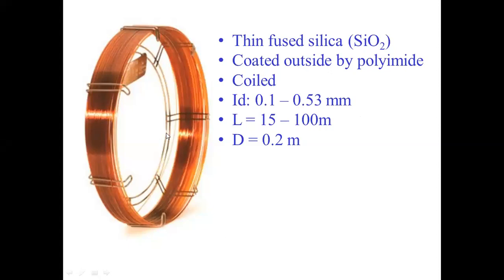And the intensity of this brownish color will fade away with time. So depending upon the intensity of this brownish color, we can decide whether the column is active or not, whether it is usable or not. The lifetime is also decided by looking at the color outside.